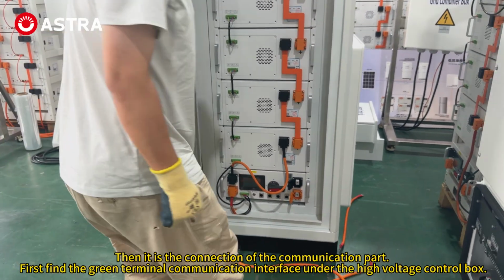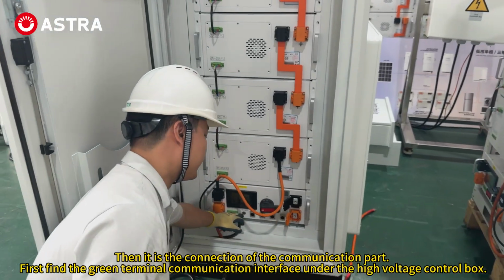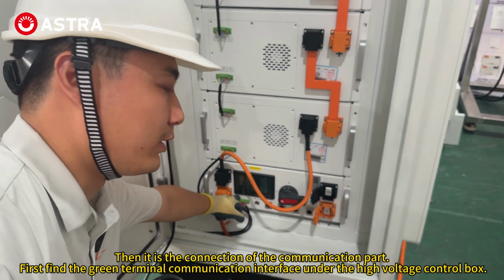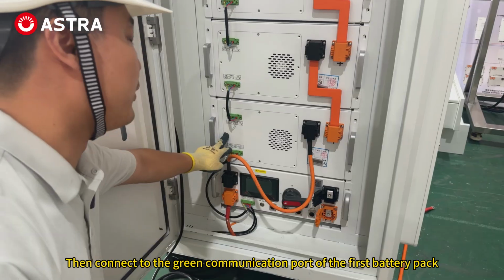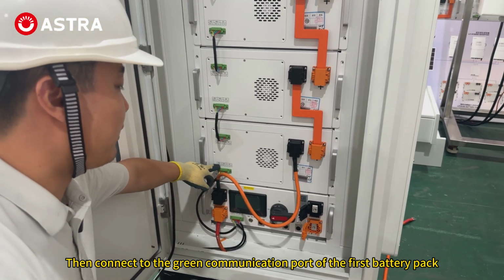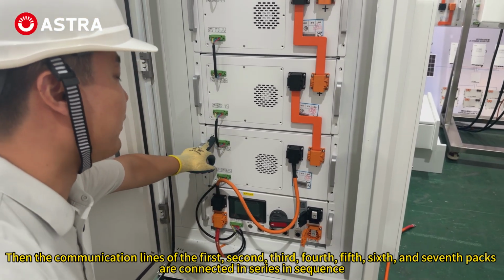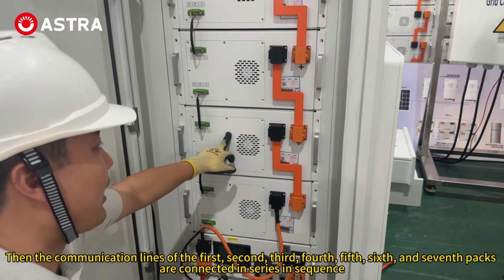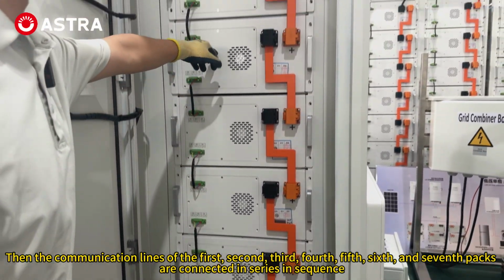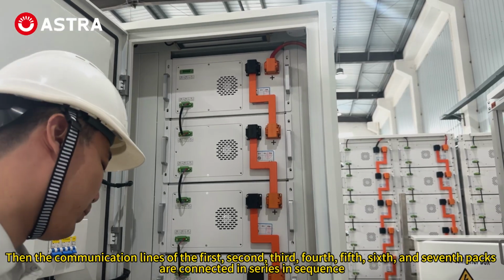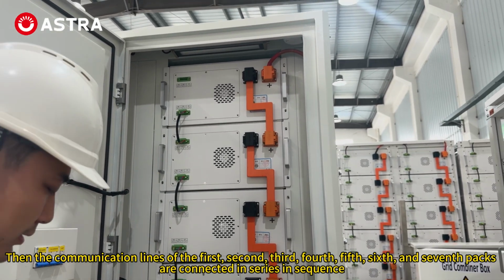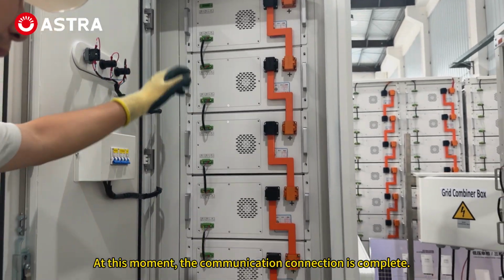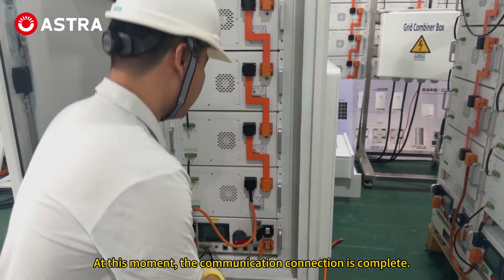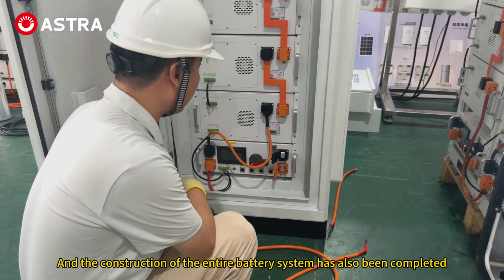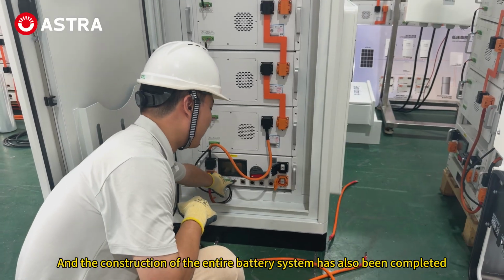Then it is the connection of the communication part. First find the green terminal communication interface under the high voltage control box. Then connect to the green communication port of the first battery pack. Then the communication lines of the first, second, third, fourth, fifth, sixth, and 7th packs are connected in series in sequence. At this moment, the communication connection is complete. And the construction of the entire battery system has also been completed.